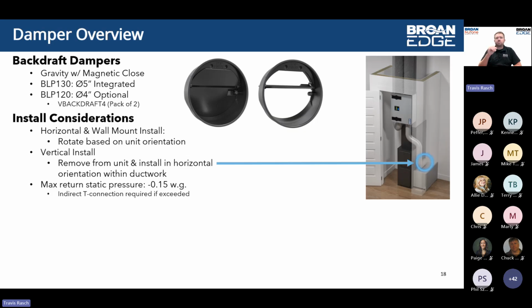One other thing to note, and it's not really too prevalent, but it's something to mention, on the return side. Depending on how you're going to duct this, we want to make sure our return static pressure maintains below that negative 0.15 inches of water column. If we get in a situation where our return static pressure is higher than that value, there is the ability to put an indirect T connection into that ductwork, and basically reduce that overall return static pressure to be within that range. This is all in the manual, and again, nothing new.